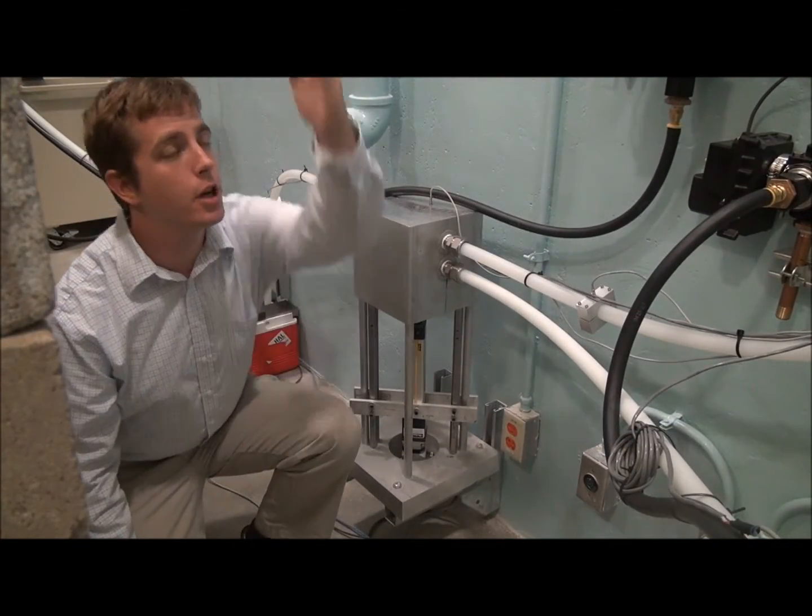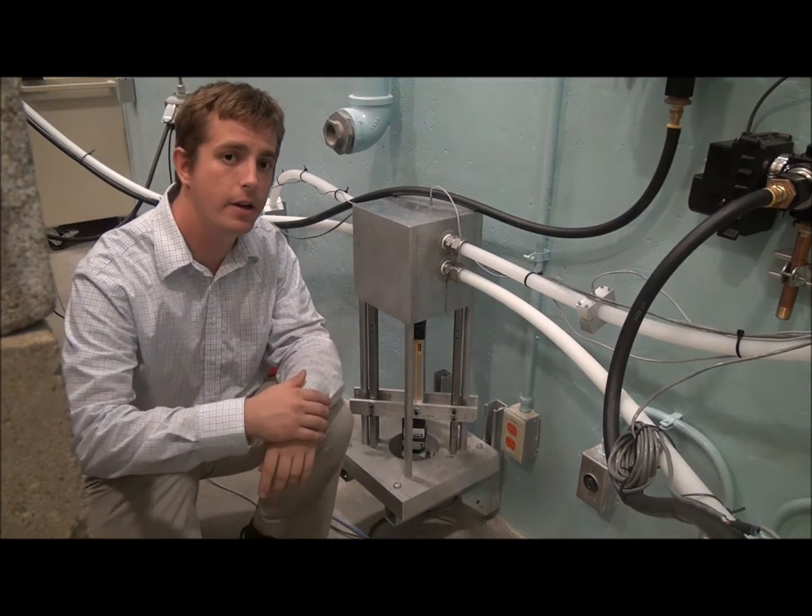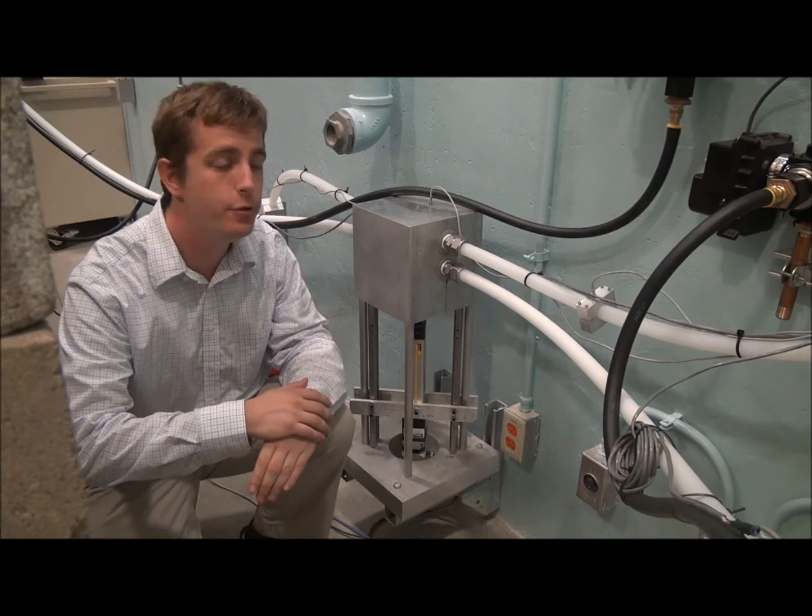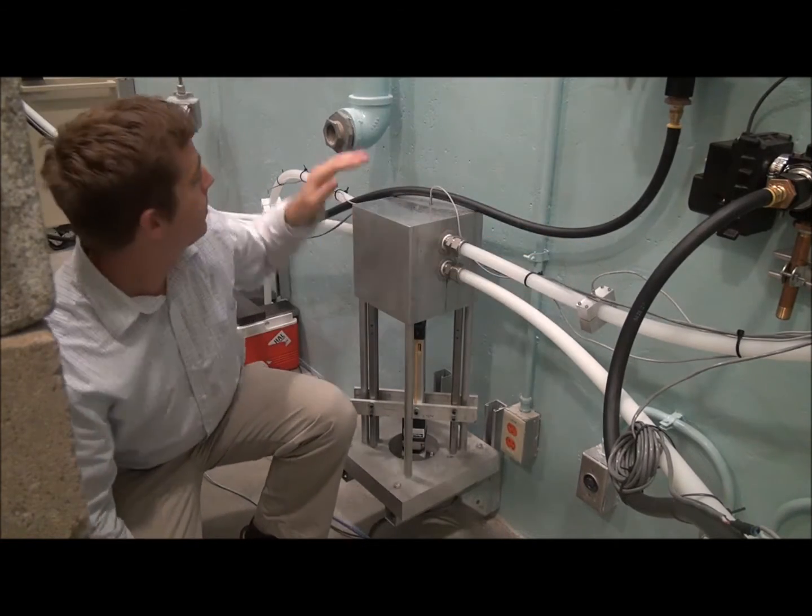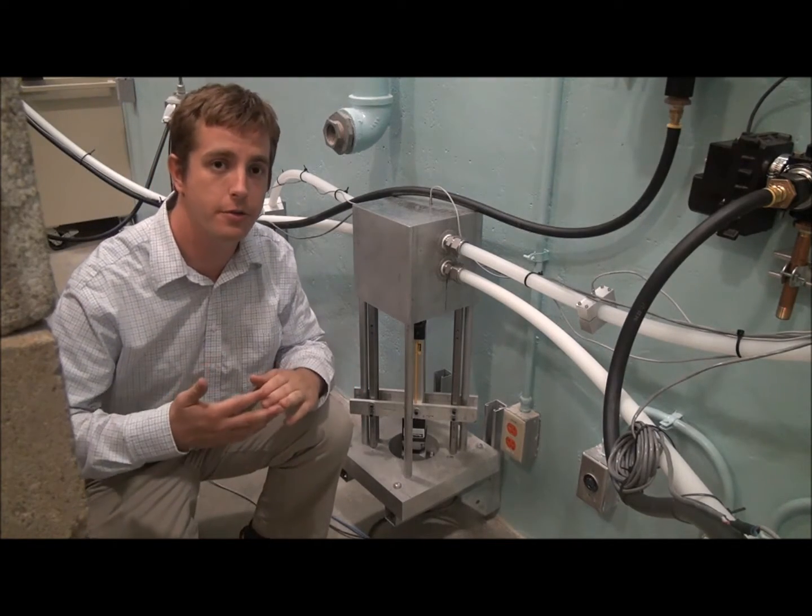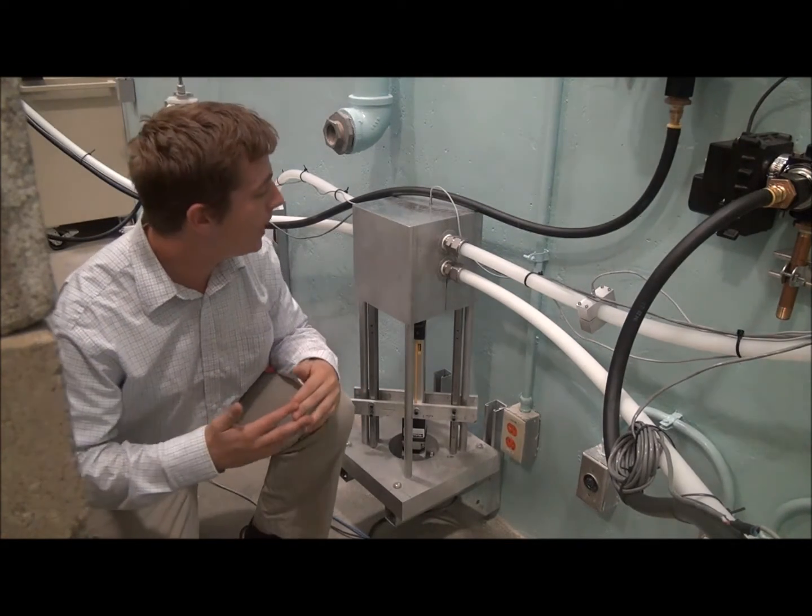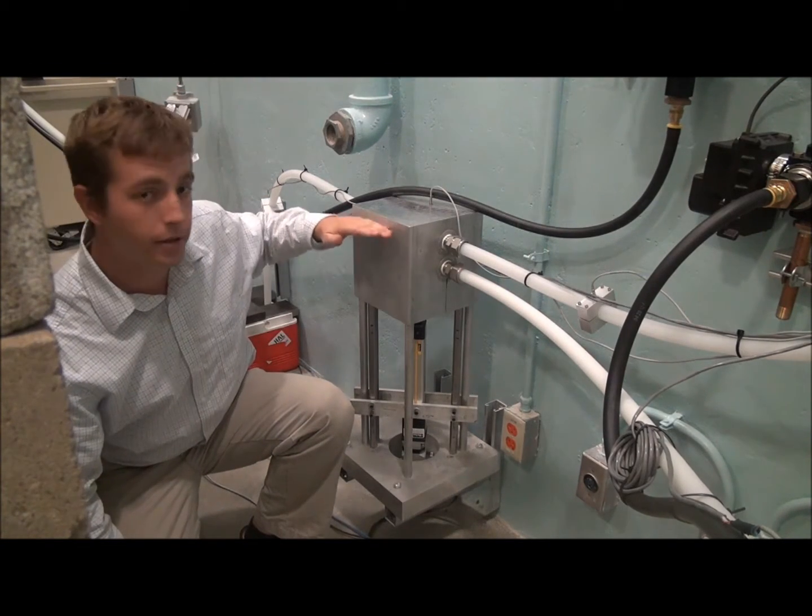Once the sample comes over the wall, it enters what we call the elevator right here. Basically, we have two pneumatic tracks. One track goes from the loading mechanism to the waste. The other track goes from the neutron generator to the germanium detector. The elevator basically takes the sample and switches it from track to track.